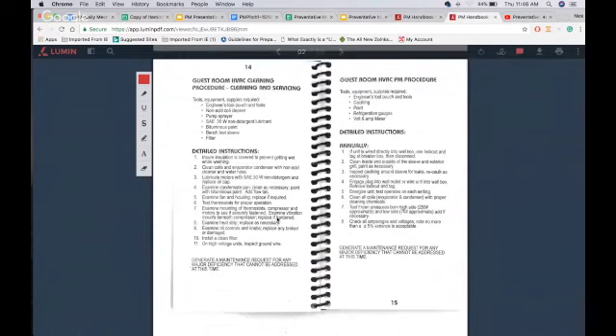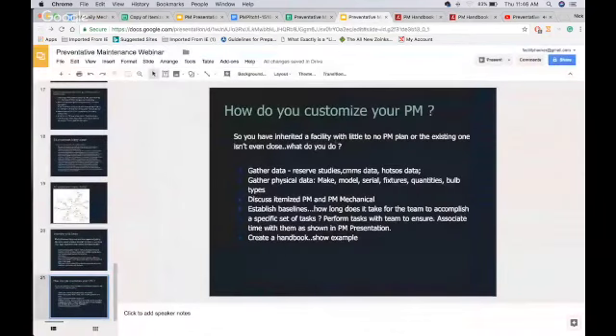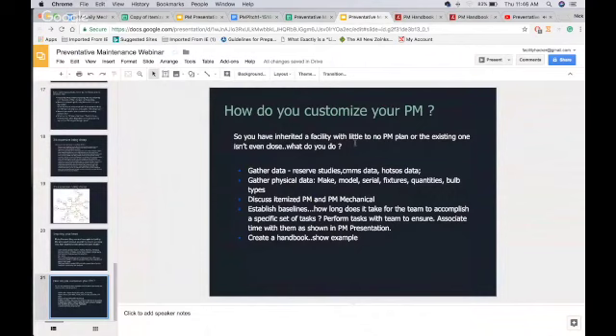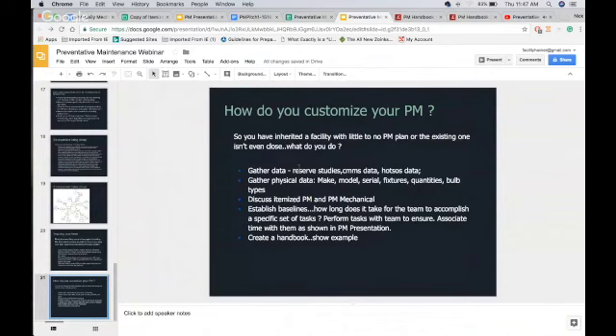How do you customize a PM program? Most of us have inherited a facility with little to no PM — or not a very robust one. You begin to gather data in the form of reserve studies, CMMS, HotSOS, or even handwritten logs you compile and analyze. You become a data scientist and understand the systemic issues on your property, where your failure points have been, and where you need improvement. You also gather physical data — a long process where staff document make, model, serials, fixtures, quantities, bulb types, oil types, whether it has a zert fitting — all the specific physical details of the equipment you're servicing.